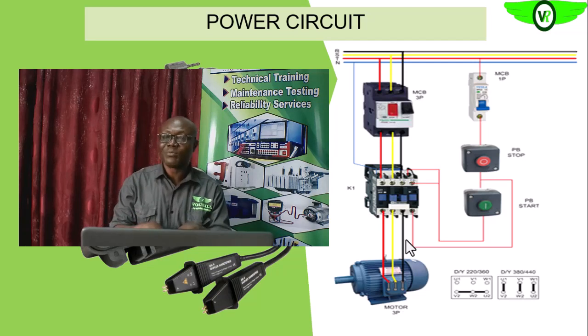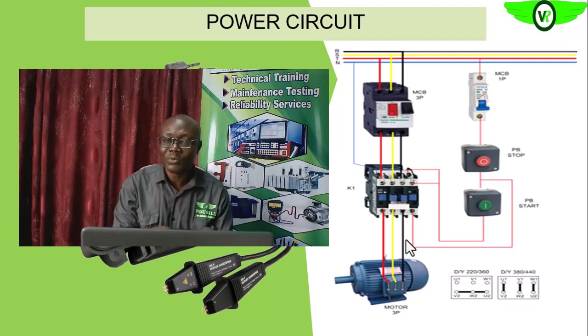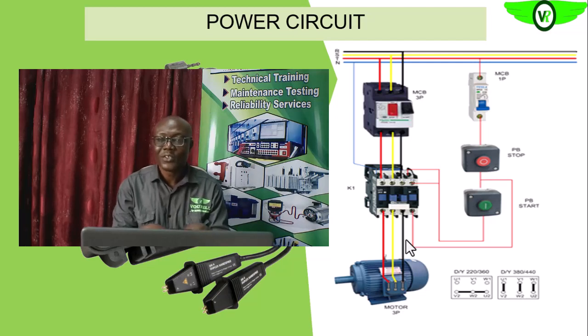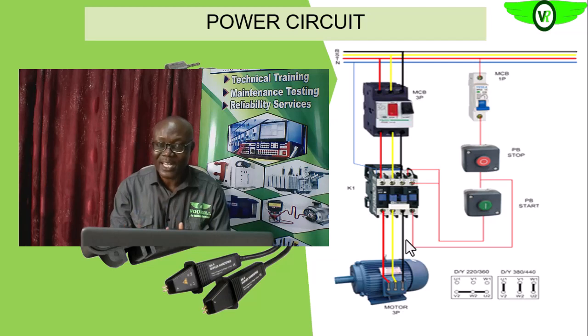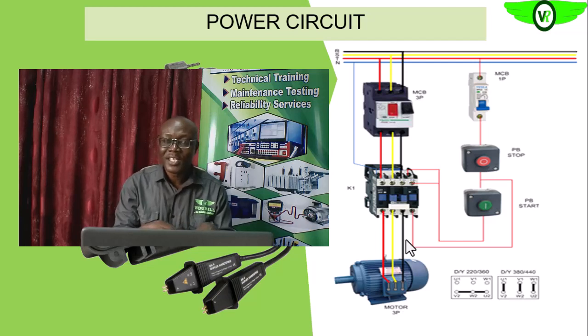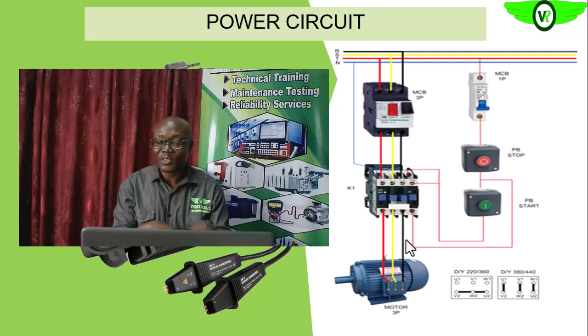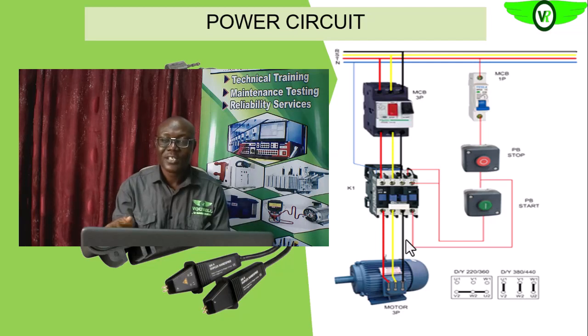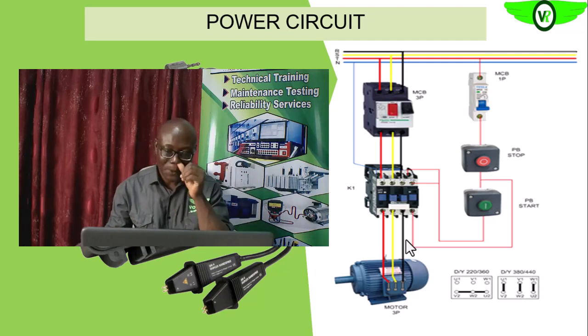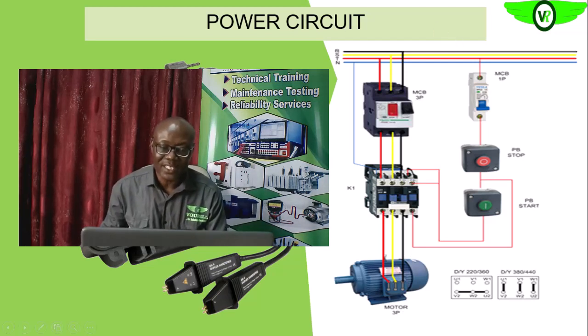unbalance is coming from within the electric motor, we need to check further, can do the winding inductance test to ascertain the level of unbalance in the inductance. Remember, the inductance will give us a better value than the resistance, low resistance meter, simply because the resistance has a linear or direct relationship with the number of turns. Are we getting it? Why the inductance has an exponential relationship, n square. Okay, so that will give us a better idea of what is happening within the power circuit.